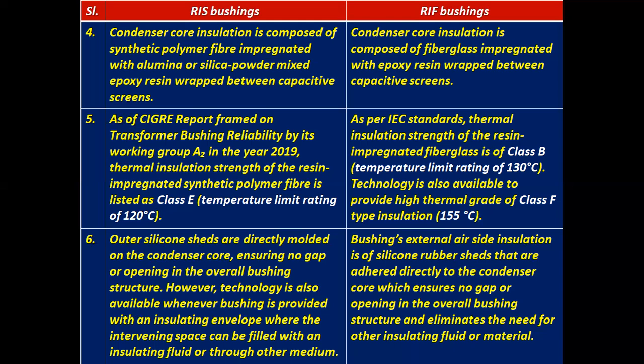But for RIF bushings, as per IEC standards, the thermal insulation strength of the resin impregnated fiberglass is of class B type insulation, that is a temperature limit rating of 130 degrees centigrade. Technology is also available to provide a higher thermal grade of class F type insulation, 155 degrees centigrade.